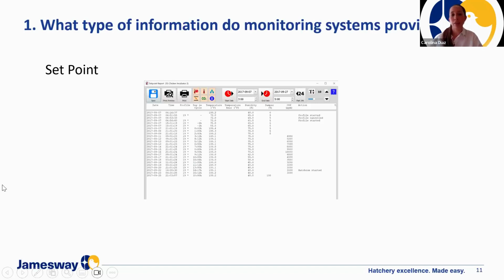And also if it was done at the correct time, because things can happen, and sometimes we have seen cases where the calibration was done, for example, at day 15 or 16, when the damper is already open. So it won't be as exact as when you do it with the damper closed, no heating or cooling activation, and the machine very uniform and stable.